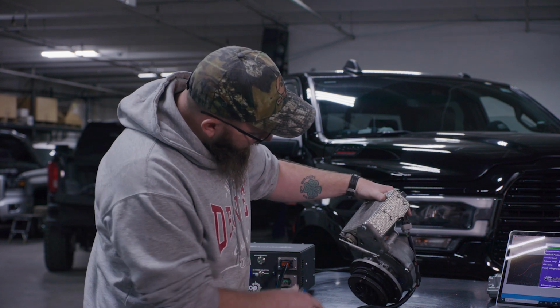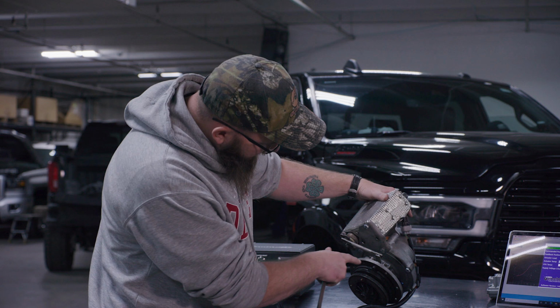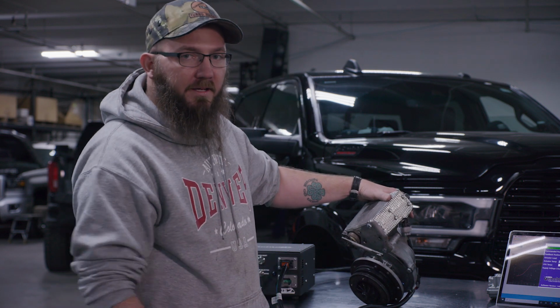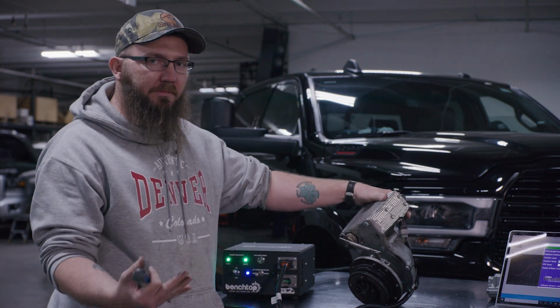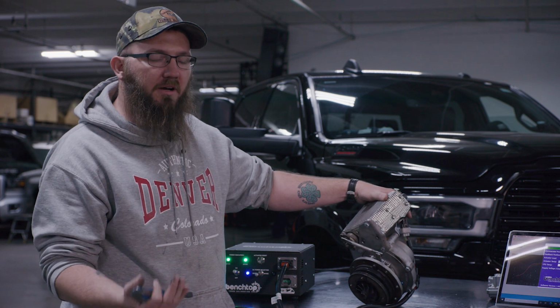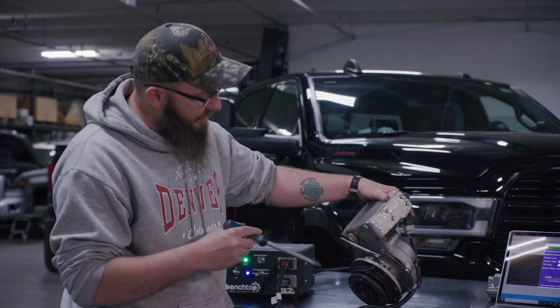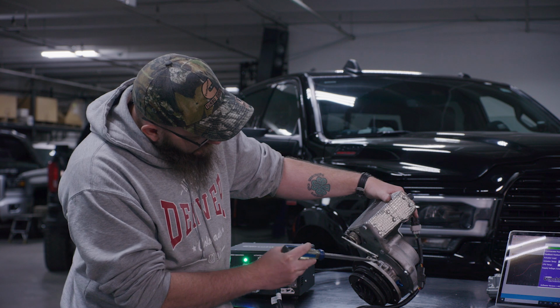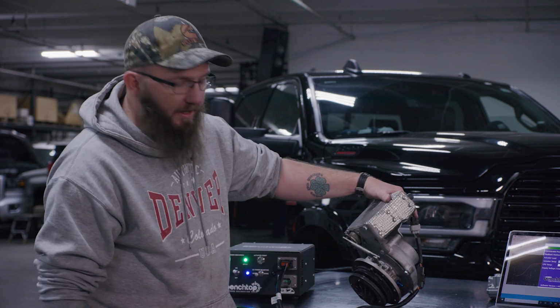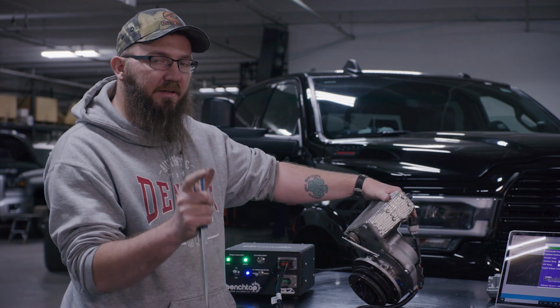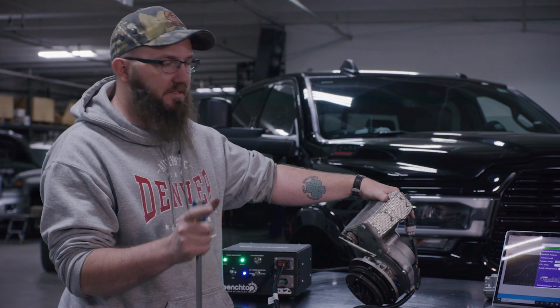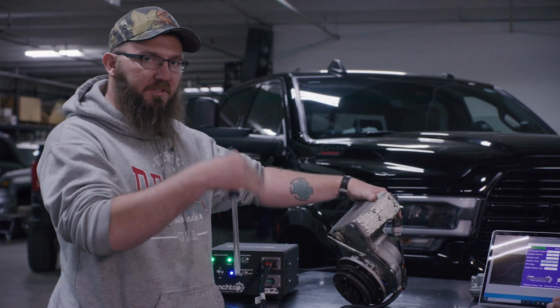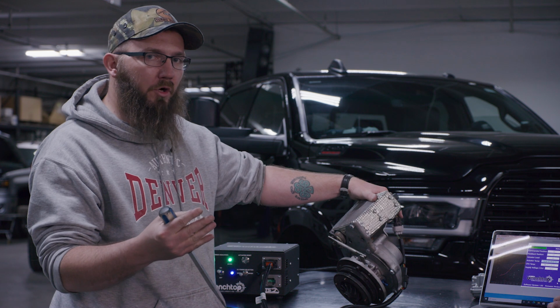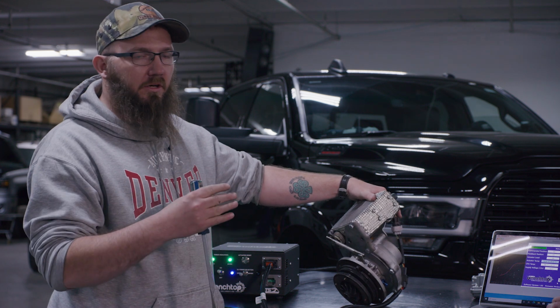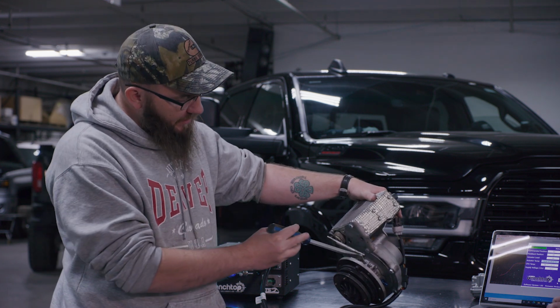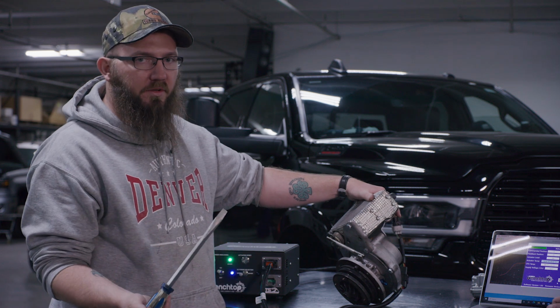See if it works. It should now stop right there. That's what the whole actuator is doing. So when you rebuild the actuator, or pull that actuator off, you want to recalibrate it, because as you can see, the new set point stops quite a bit off. Now it's rescaling, readjusting that span of what 0 to 100 means, from 0 being closed, 100% being open. The range it can actually go is readjusting based on the limited position I created with the screwdriver.